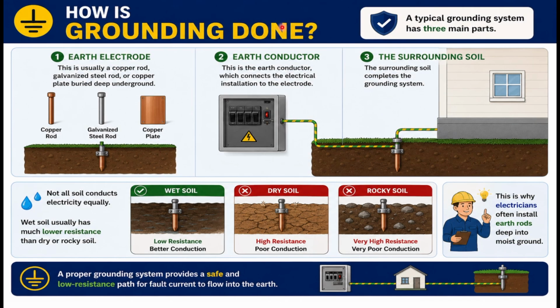So, how is grounding done? Firstly, grounding is done by burying an earth electrode into the ground. We have different types. The most common is the copper rod. We also have copper plates that are buried in the ground. After burying it in the ground, you measure the resistance using an earth resistance tester. You test the resistance until you are sure that it is in the range of the required resistance, which for domestic installations is 10 ohms and below, and for industrial cases it should be, I think, 5 ohms and below. Once you measure that, you connect your earth conductor to it.